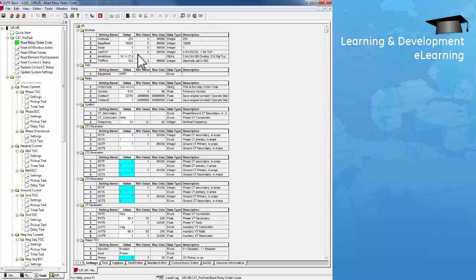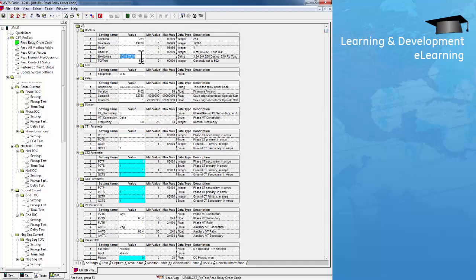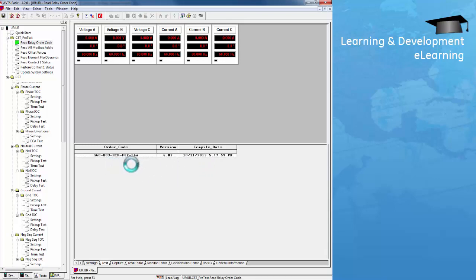To run this database, first we need to read the relay order code. Enter the IP address of the relay under the Modbus folder and run read relay order code. This test will read the relay order code, firmware version, and compile date. We can see it's a UR G60 with firmware version 6.02.